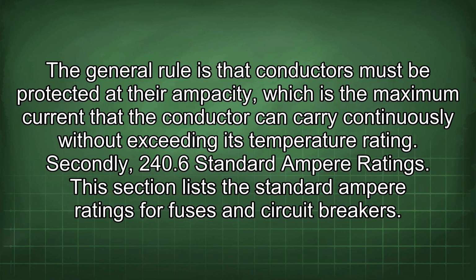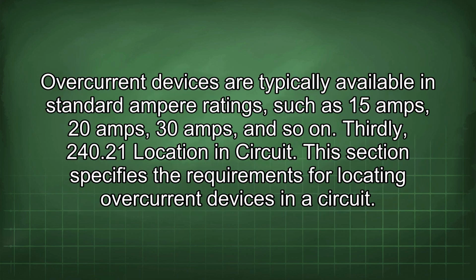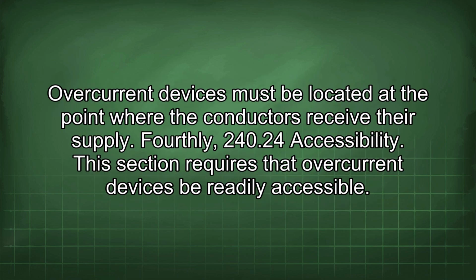Secondly, 240.6 Standard ampere ratings. This section lists the standard ampere ratings for fuses and circuit breakers. Overcurrent devices are typically available in standard ampere ratings such as 15 amps, 20 amps, 30 amps, and so on. Thirdly, 240.21 Location in circuit. This section specifies the requirements for locating overcurrent devices in a circuit. Overcurrent devices must be located at the point where the conductors receive their supply.